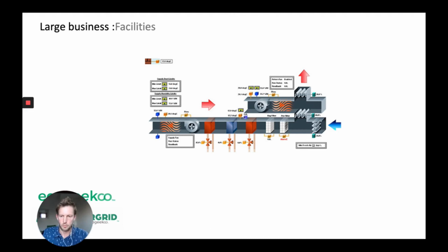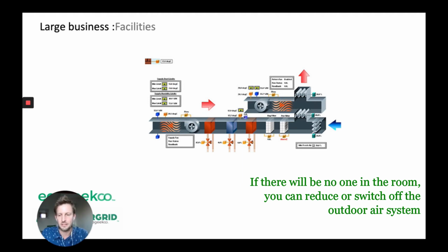So often buildings throughout set points of occupancy, so maybe an office day, will be drawing in a lot of outdoor air and ramping that up or down according to the number of occupants in the building. The set points being called for, or what are called CO2 sensors, which are often a measurement of how full a room is. So it can say, hey, this room's producing X amount of CO2, that must mean X amount of people are there, therefore bring in more fresh air so they don't go to sleep. If you haven't got any users in the room, you might have nobody in the building, these systems become redundant.